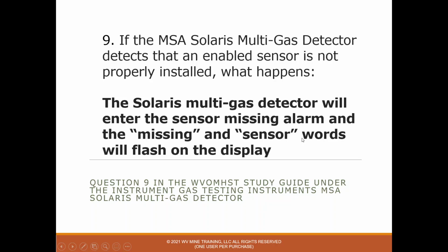Question 9, if the Solaris multi-gas detector detects that an enabled sensor is not properly installed, what happens? And that is the Solaris multi-gas detector will enter the sensor missing alarm, and the missing and sensor words will flash on the display. So it will be obvious to you. I've actually seen that before, and you'll quickly realize that there's something wrong.